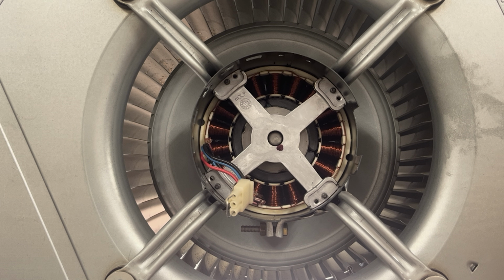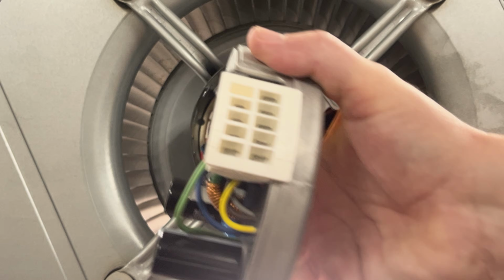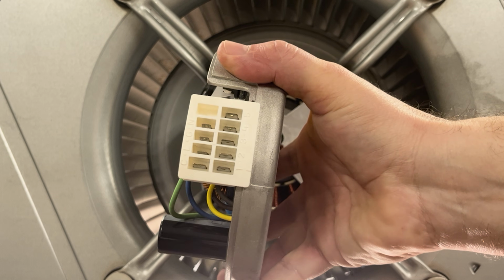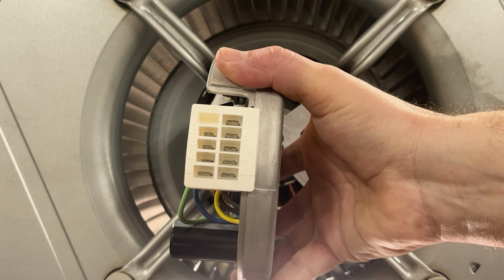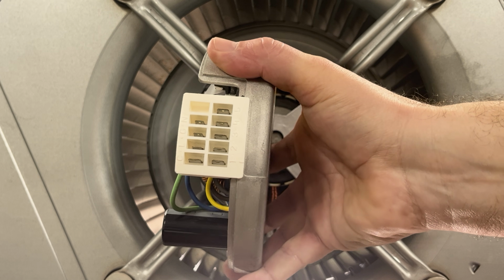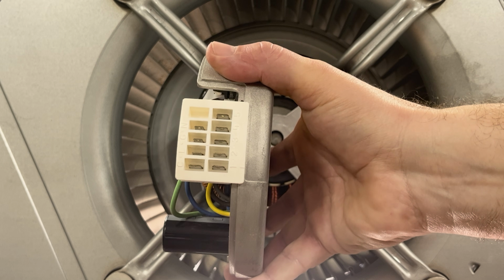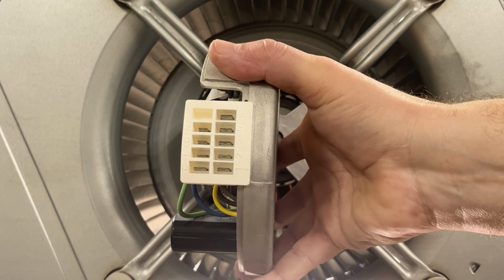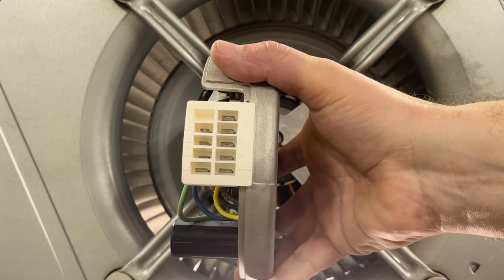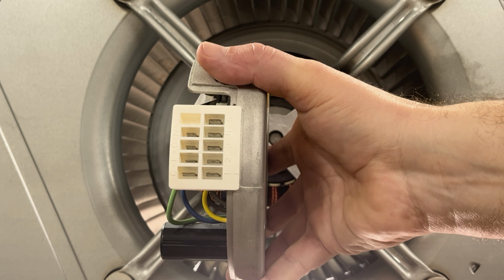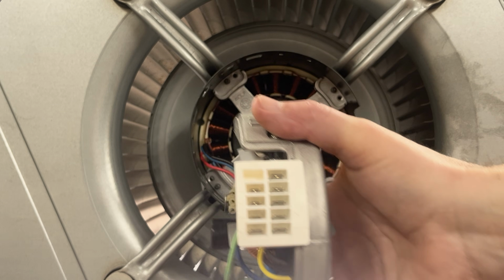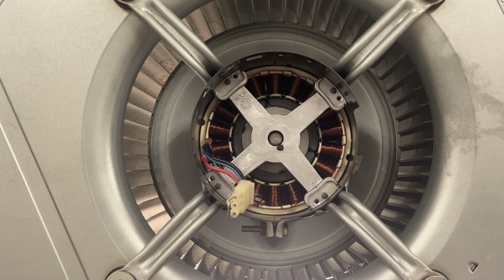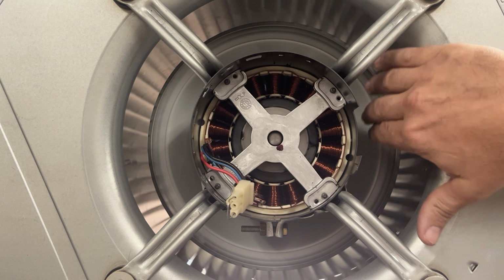So this would say, hey, in the event that my motor was not running and I went through terminals 1 through 5, and I tested 24 volts on each one of those, and I had a good common back to my transformer, and between L and N I had 230 volts. If I had 230 and I had 24 volts input on 1, 2, 3, 4, or 5, and this motor would not come on, before I would condemn the motor, I would pull the module off the back of it, and I would just test to see if I had any type of resistance.